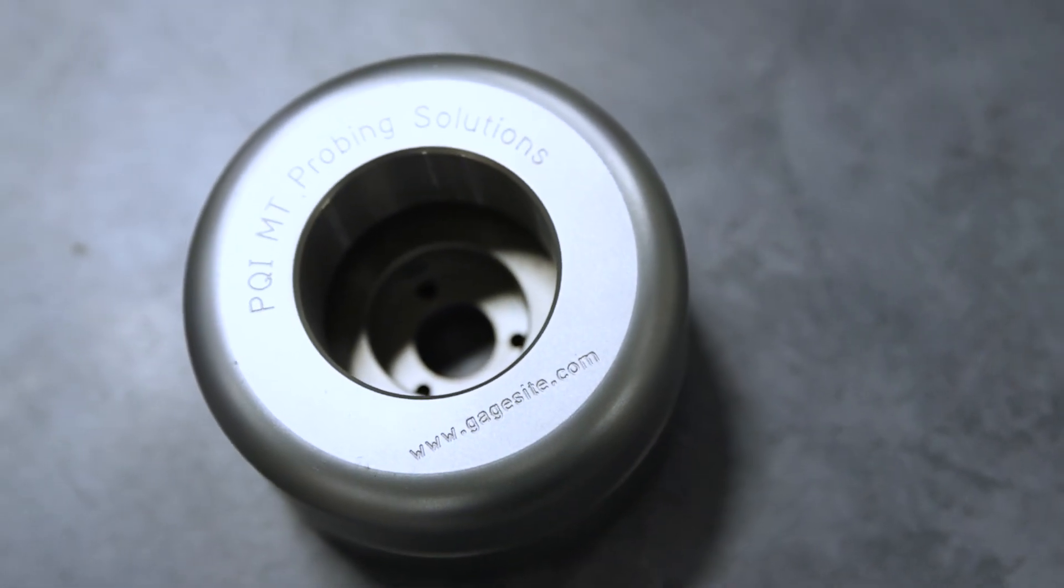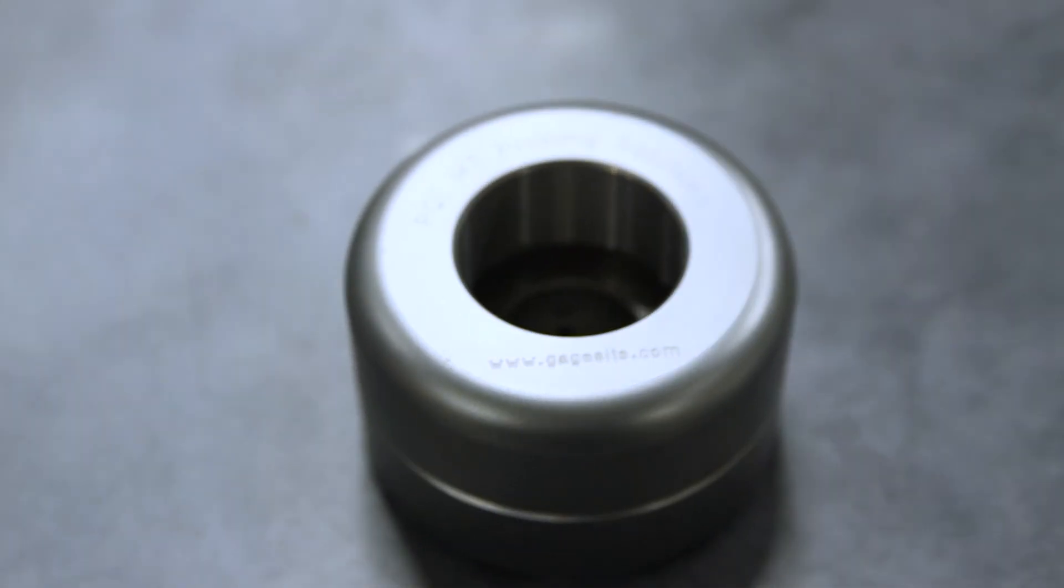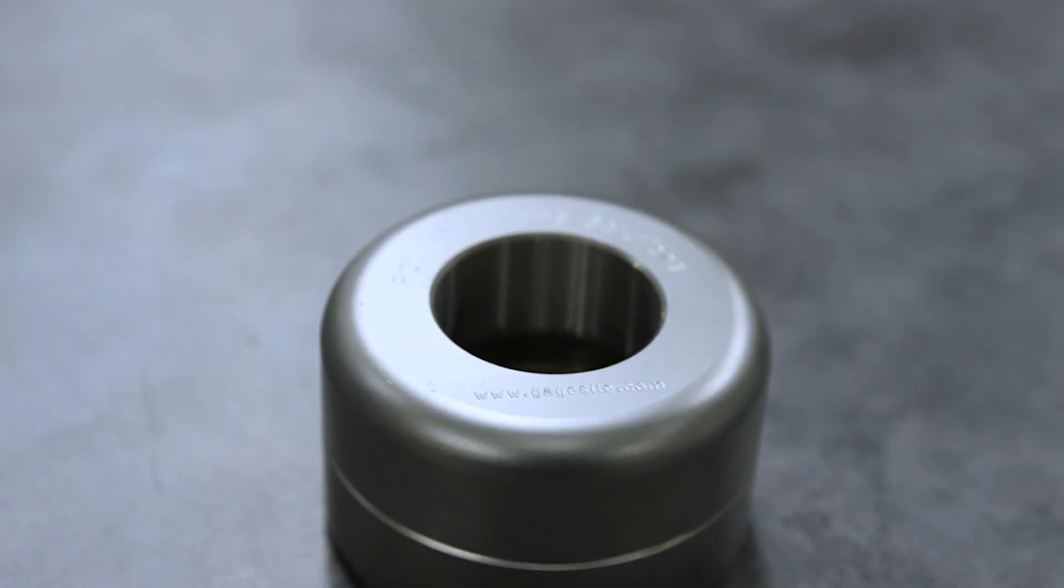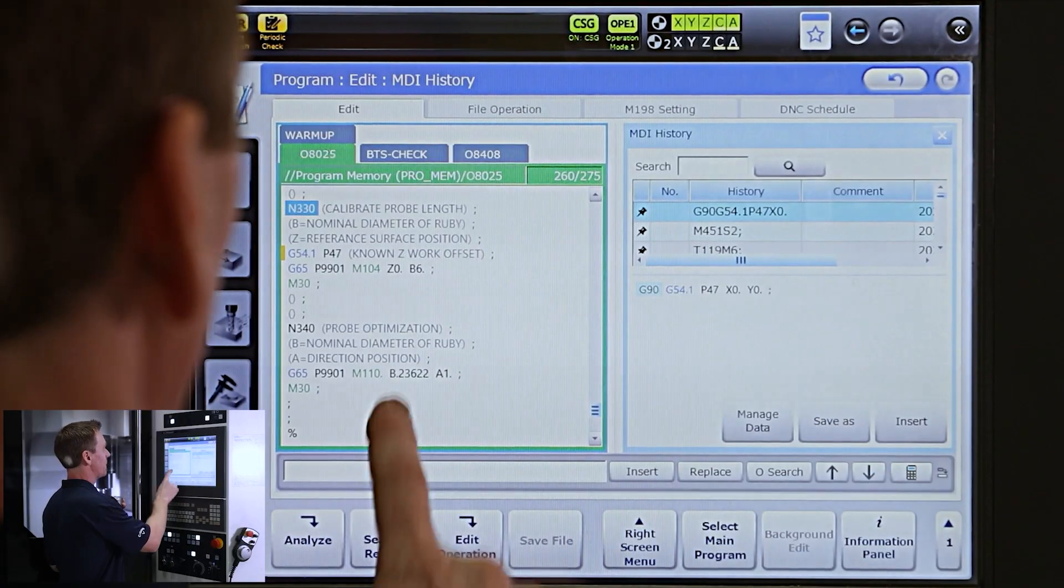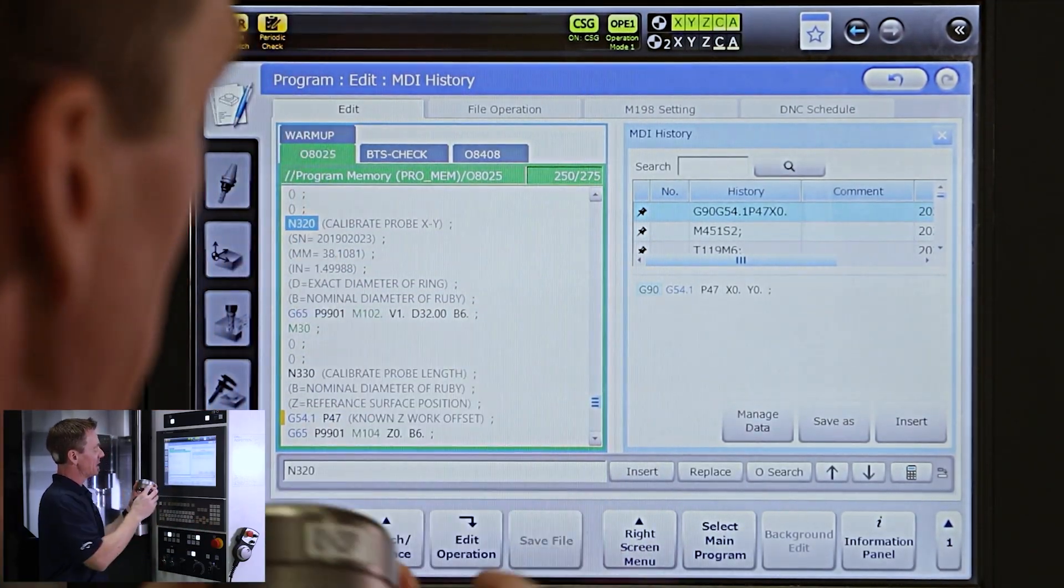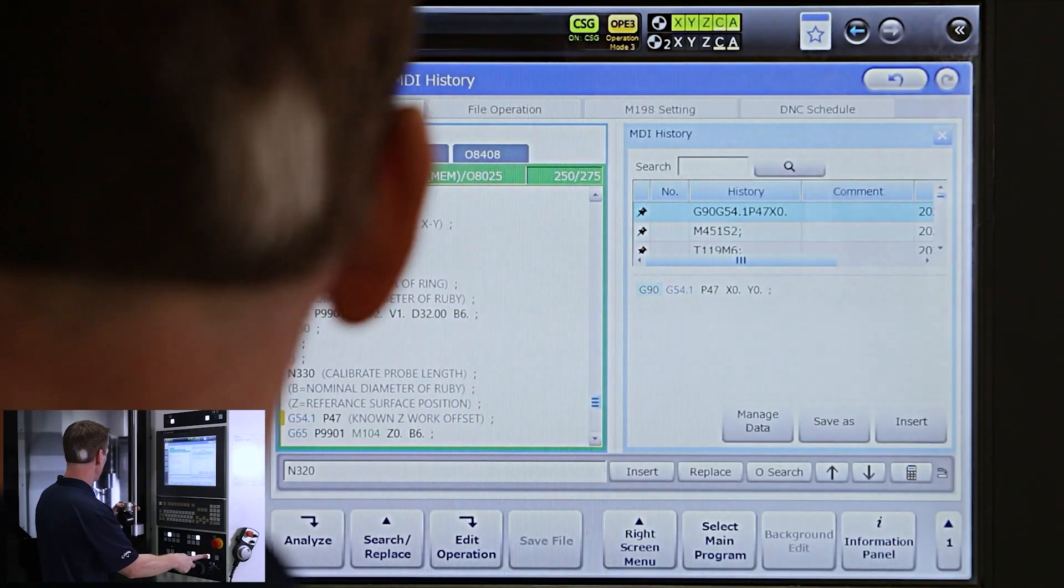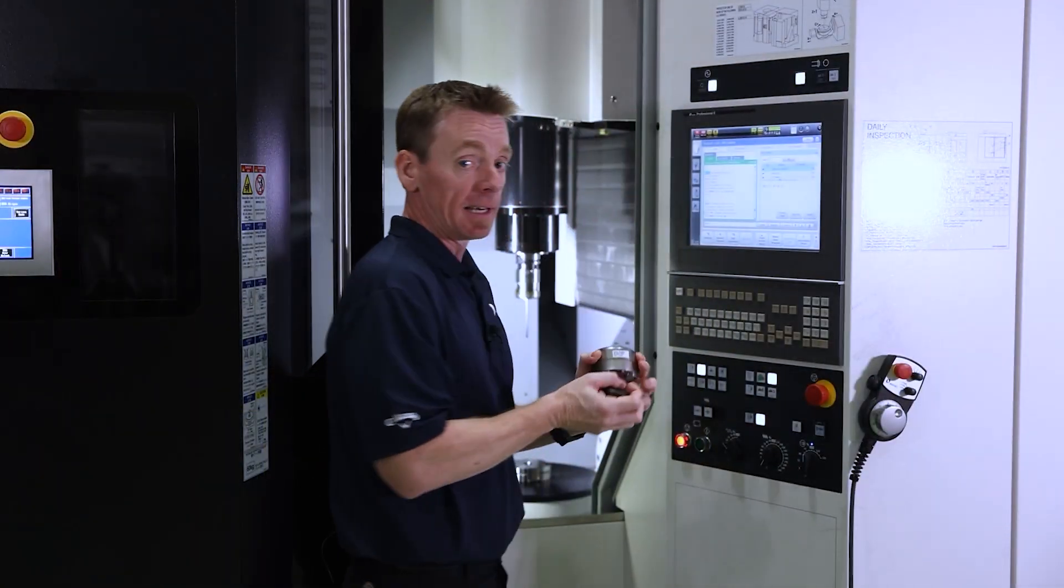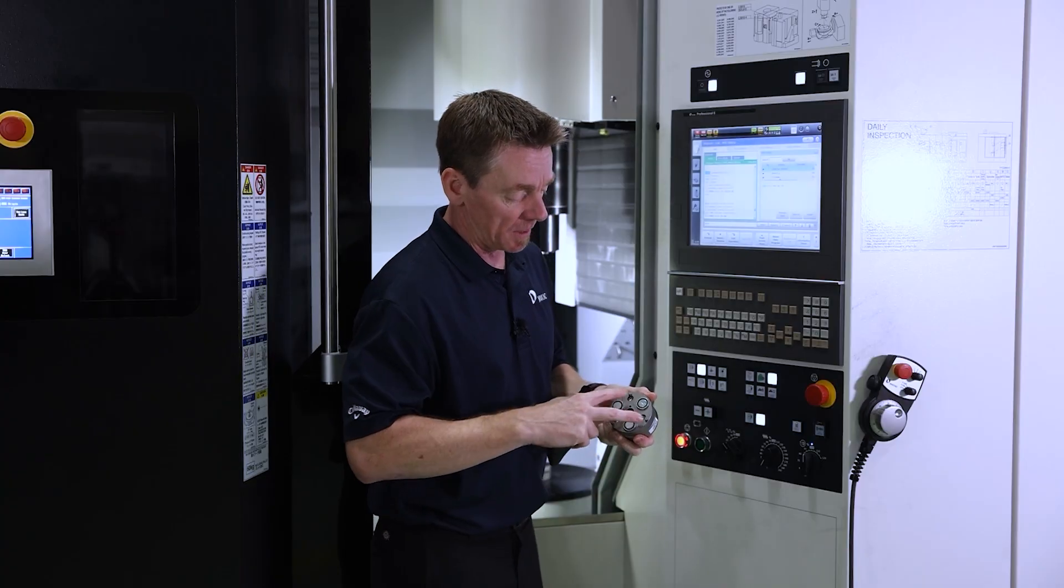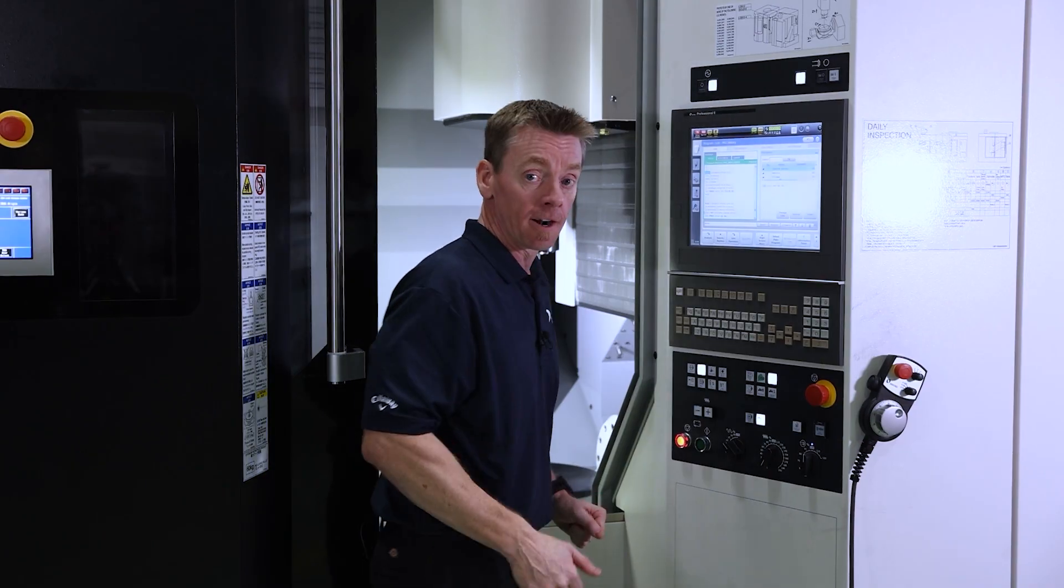So the biggest thing here is we're going to use our calibration ring that comes with the machine. It is serialized. It has all the dimensions on the side. So when we go to our 8025 program for N320, we want to make sure this information matches the sticker. We're good here. So what we're going to do is we have an empty pallet in here. We can mount this to it. It has three points of contact with magnets. It's going to suck itself on there.